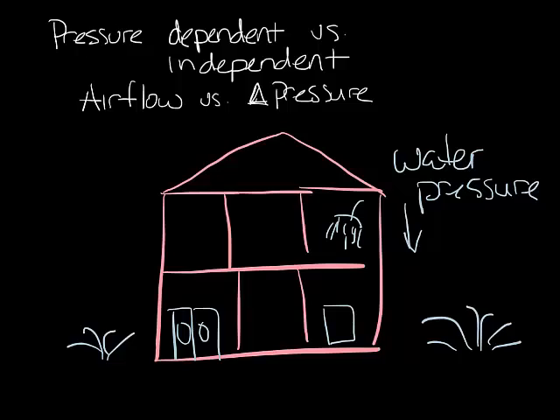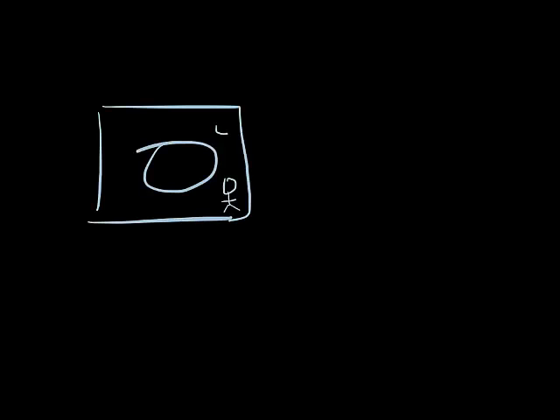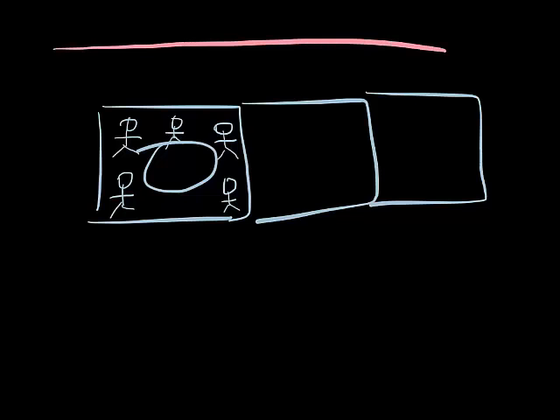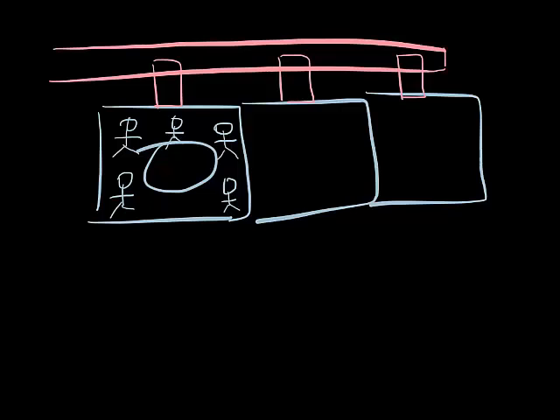Pressure dependent VAV boxes in an HVAC system work in a similar way. Going back to the conference room example from our first podcast: if the conference room goes from empty to full, it'll suddenly need a lot more air and the damper in the conference room box will open. In a pressure dependent system, if there are other offices on the same duct work, if the airflow in the conference room goes up, then the airflow in the two offices will go down because they are pressure dependent.